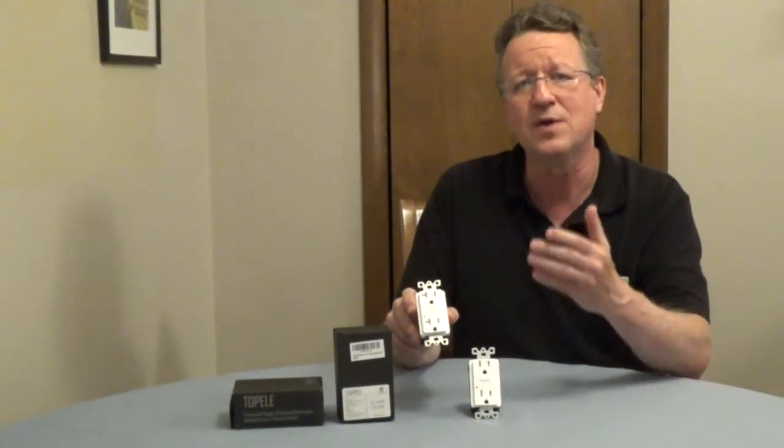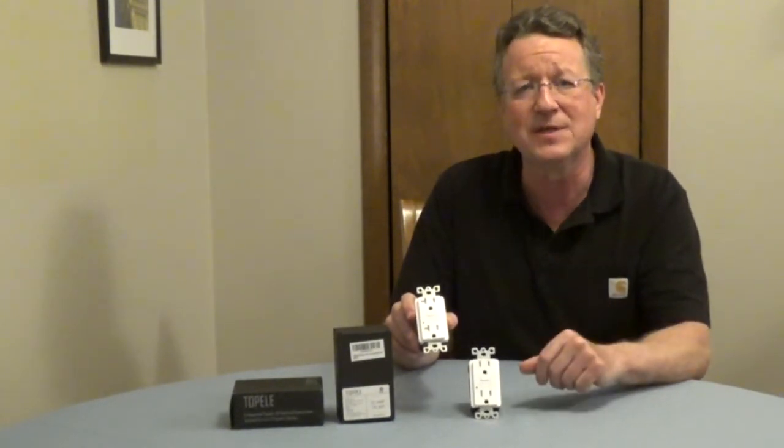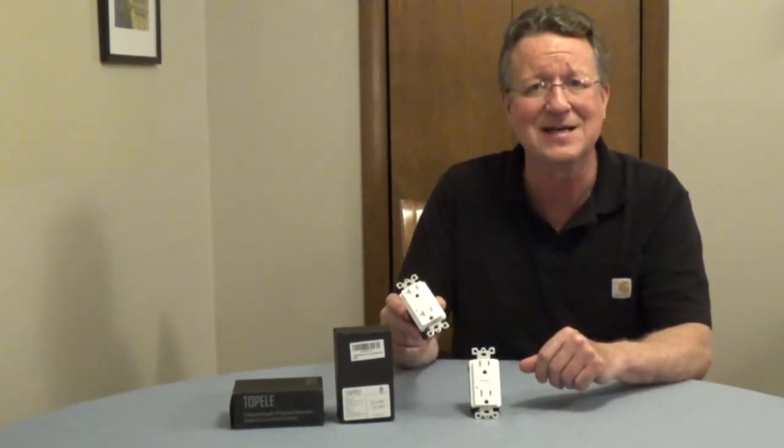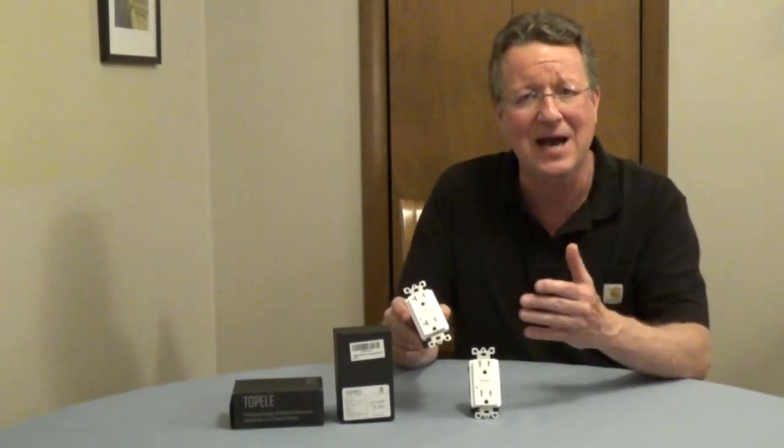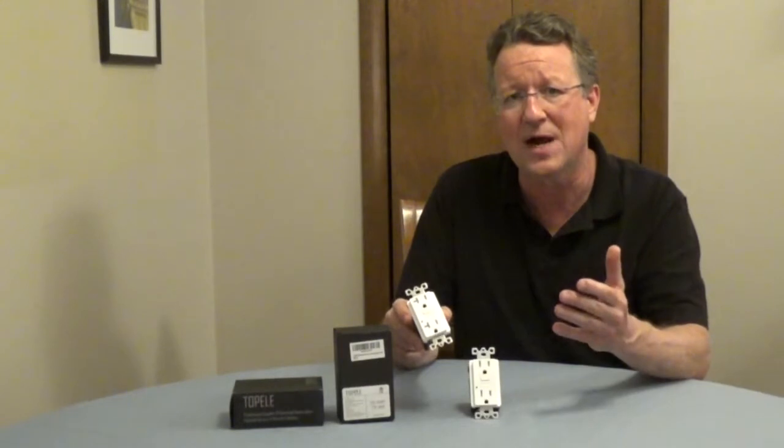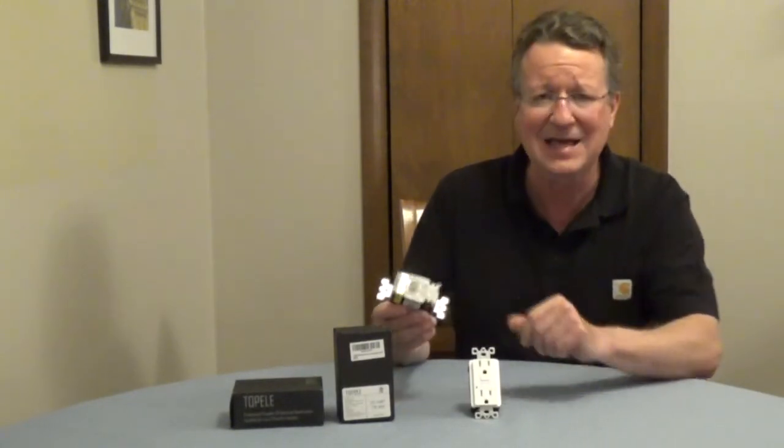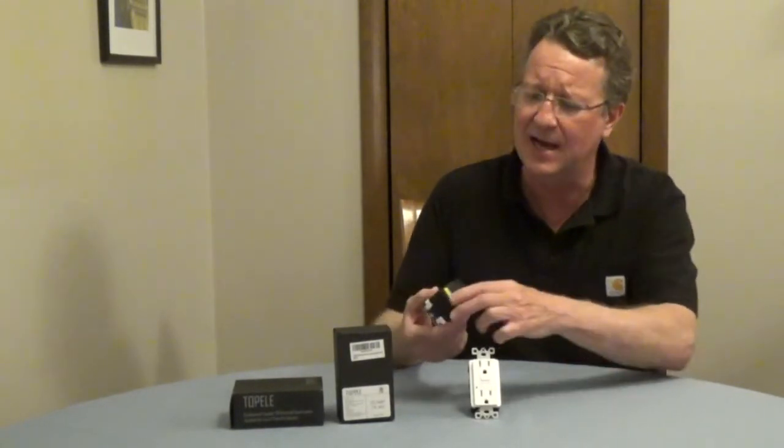The next thing you need to know is whether you have one or two cables coming into the electrical box where you're going to be connecting this. If there's one cable coming into the box, you have a hot wire, a neutral wire, and a ground, you're going to be using the line side on the back of the GFCI.